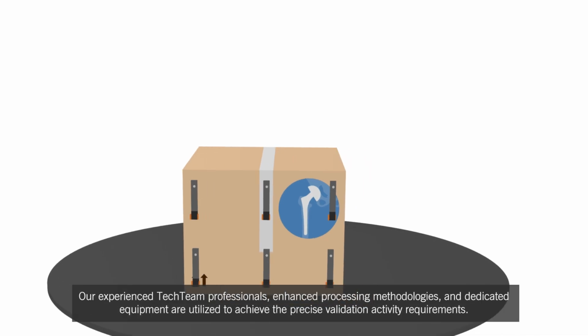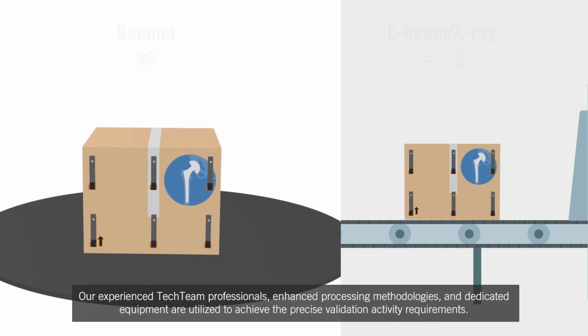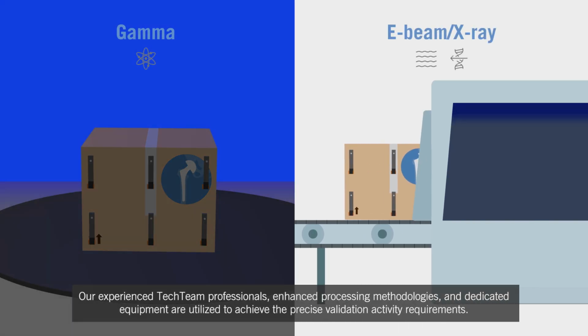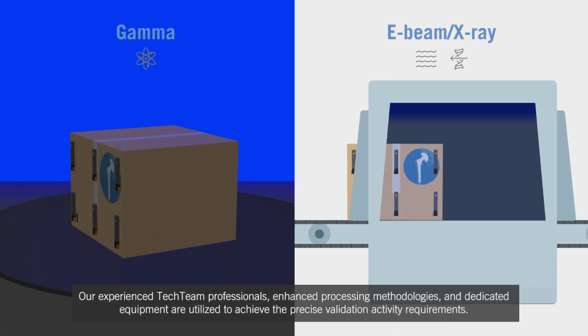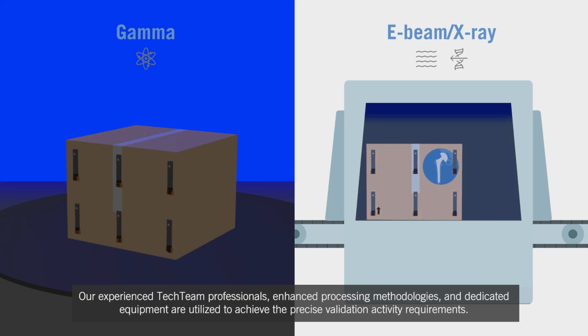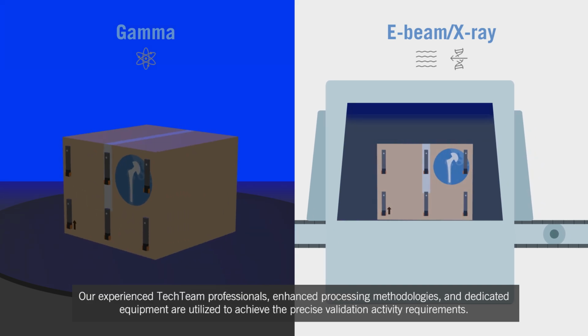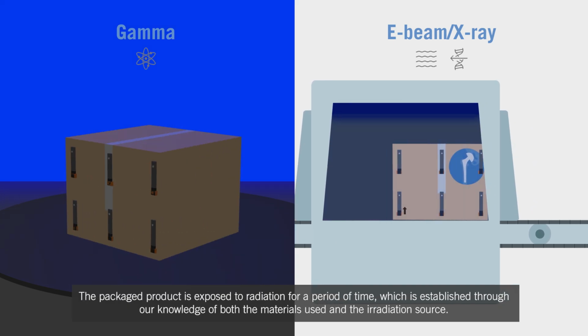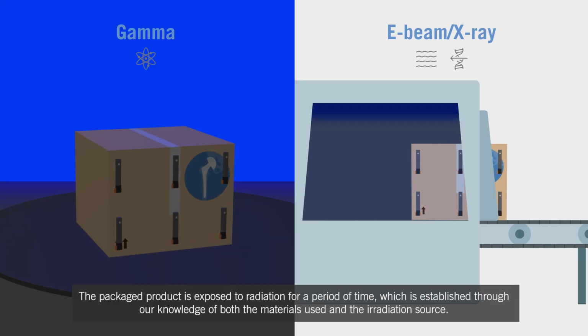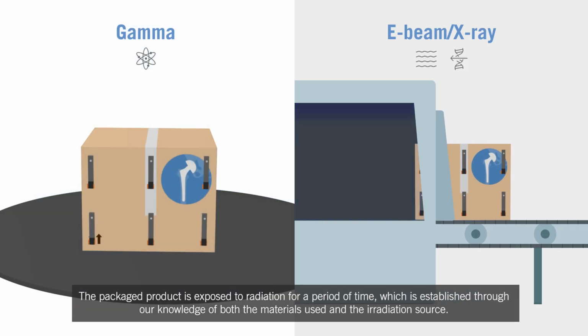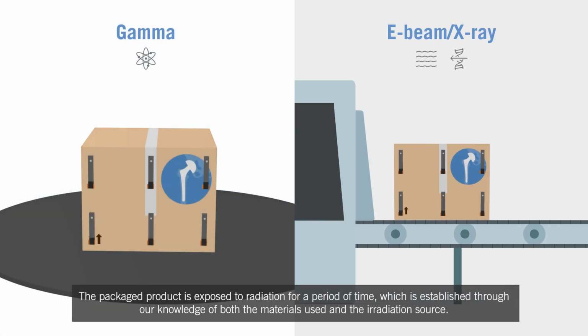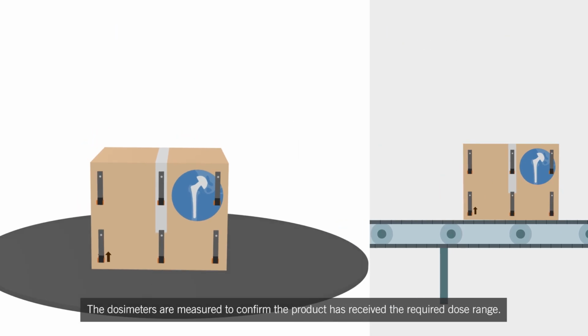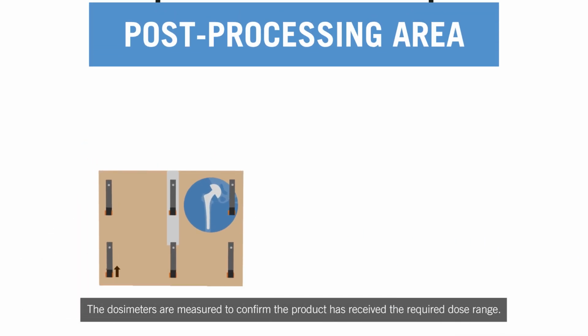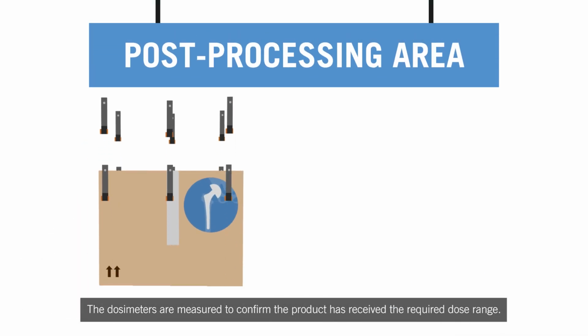Our experienced TechTeam professionals, enhanced processing methodologies, and dedicated equipment are utilized to achieve the precise validation activity requirements. The packaged product is exposed to radiation for a period of time, which is established through our knowledge of both the materials used and the irradiation source. The dosimeters are measured to confirm the product has received the required dose range.